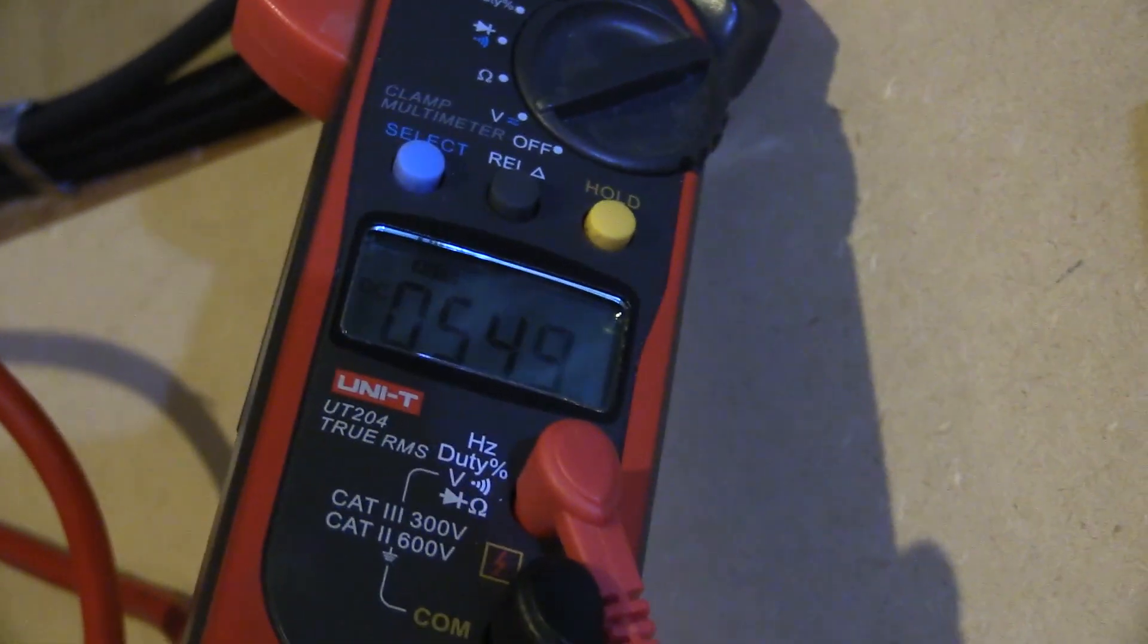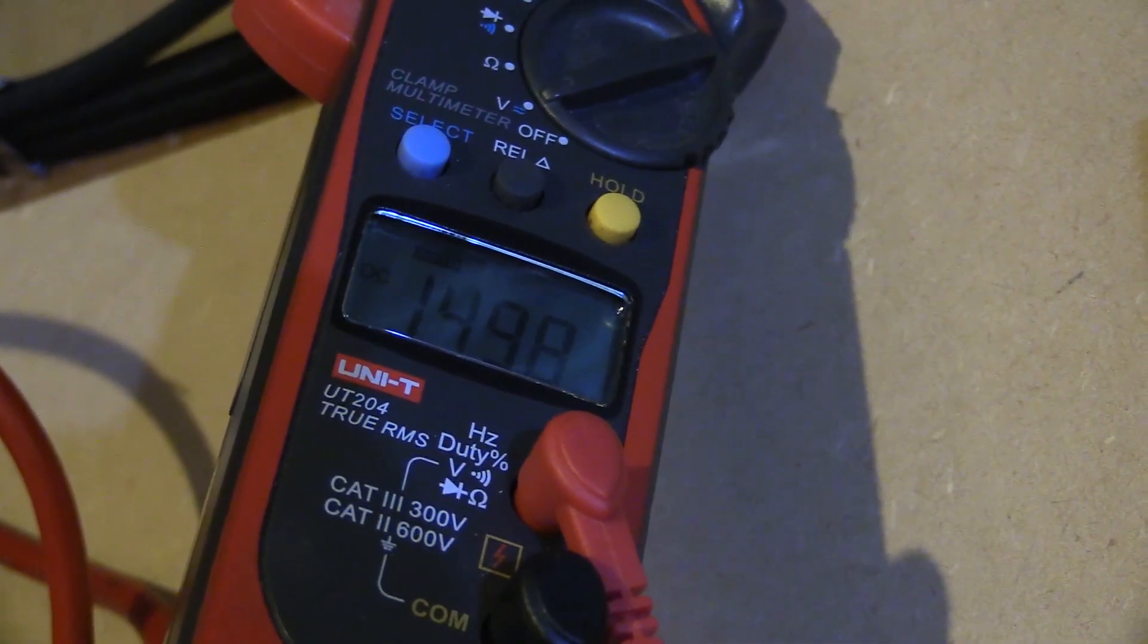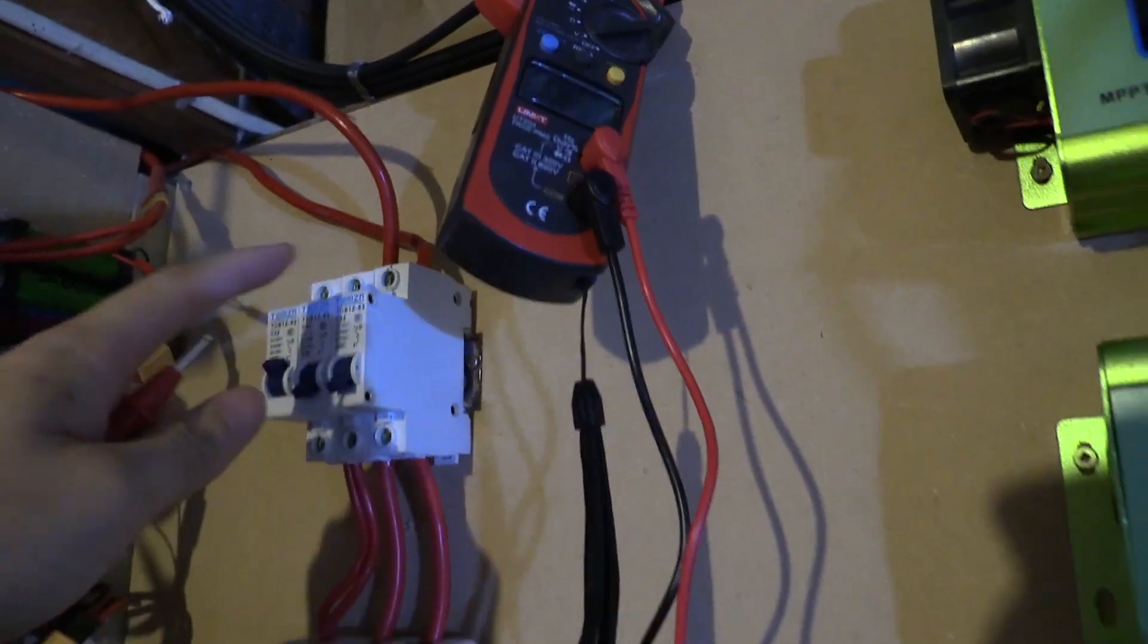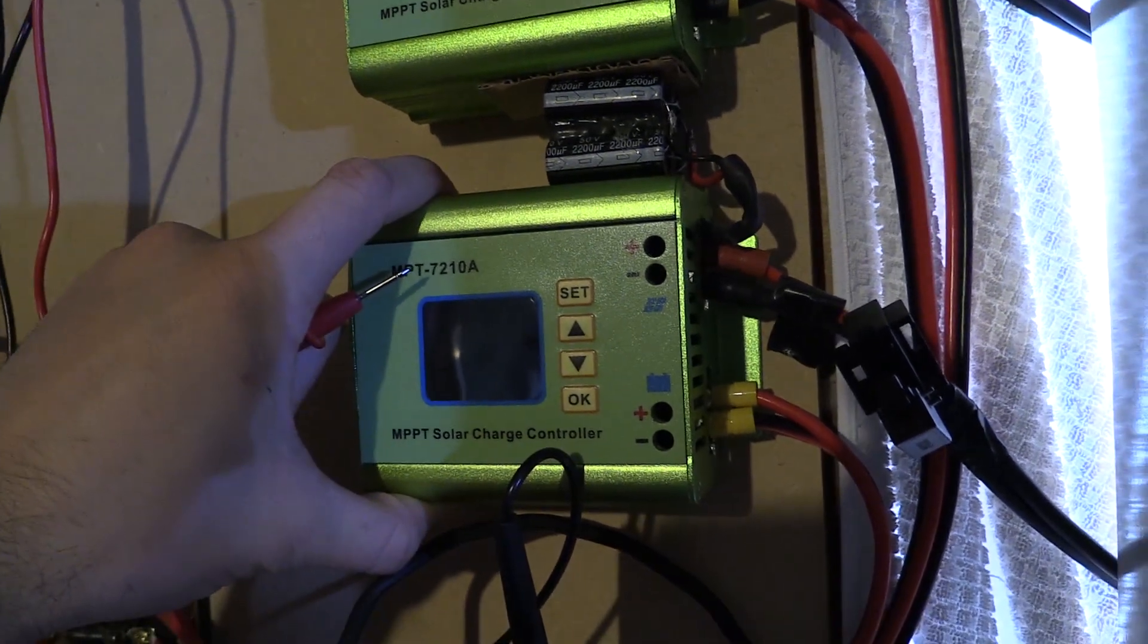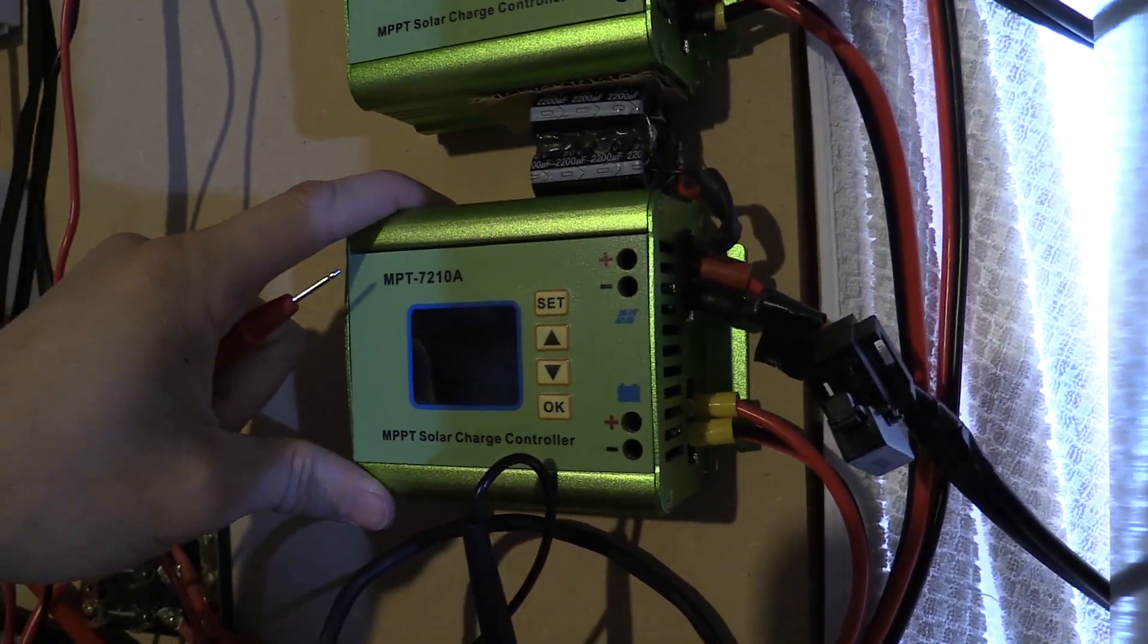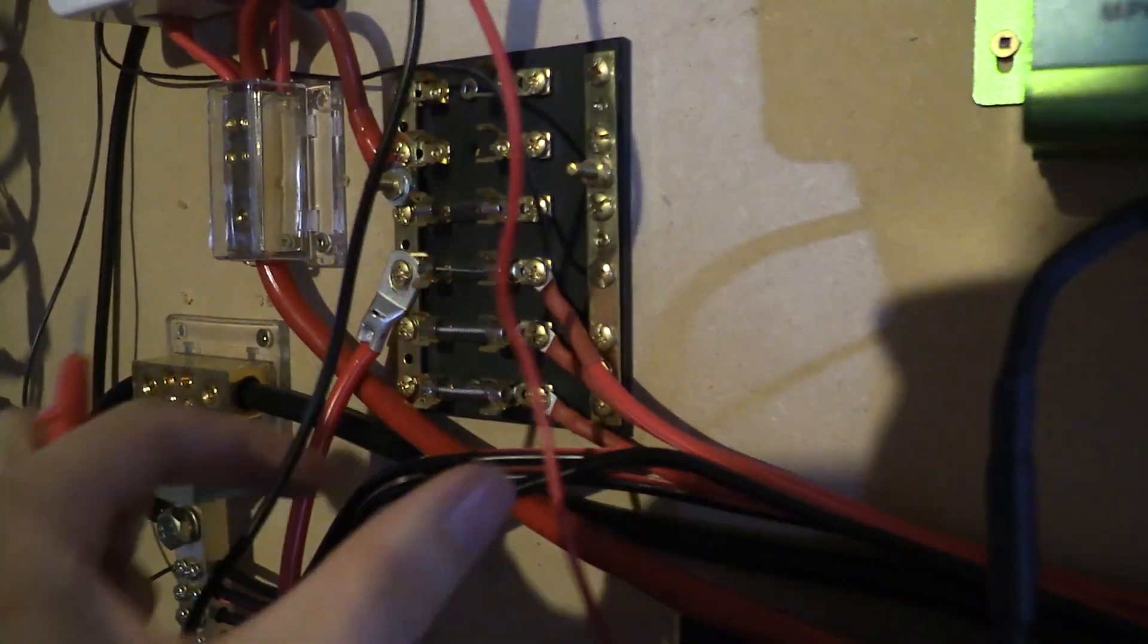I guess the next thing I do is turn the breaker on. The problem with that is if I turn this breaker on here, it's going to give power through to the DC side of these. And if the problem with this is it's blown one of the MOSFETs or something, then the MOSFET might be shorted, so that might not be the best idea.